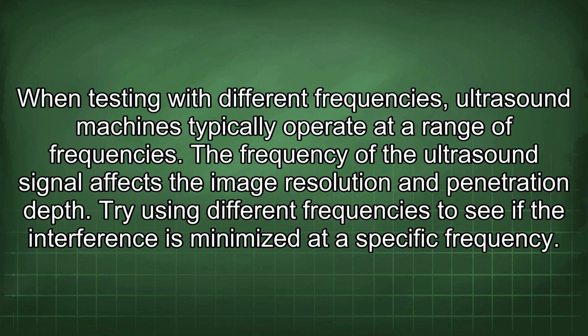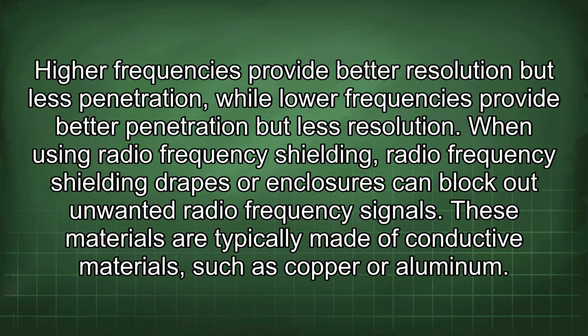When testing with different frequencies, ultrasound machines typically operate at a range of frequencies. The frequency of the ultrasound signal affects the image resolution and penetration depth. Try using different frequencies to see if the interference is minimized at a specific frequency. Higher frequencies provide better resolution but less penetration, while lower frequencies provide better penetration but less resolution.